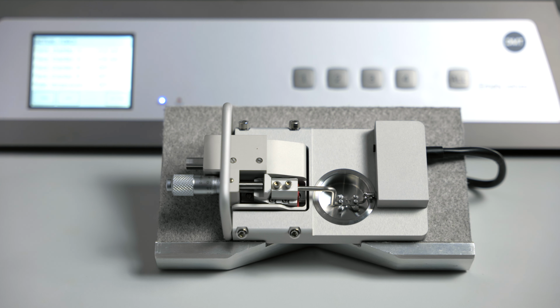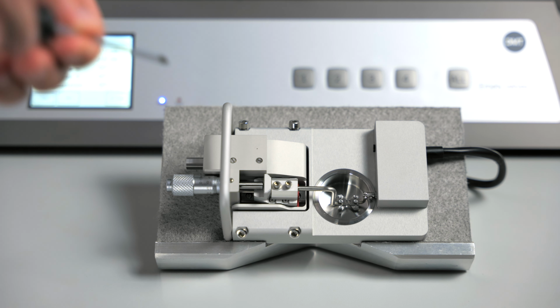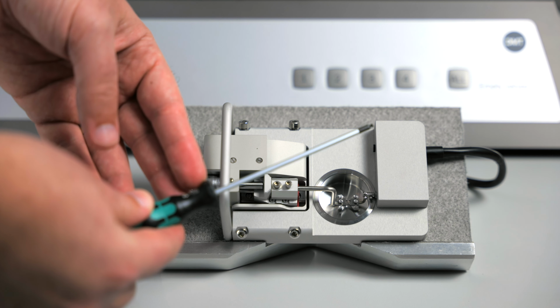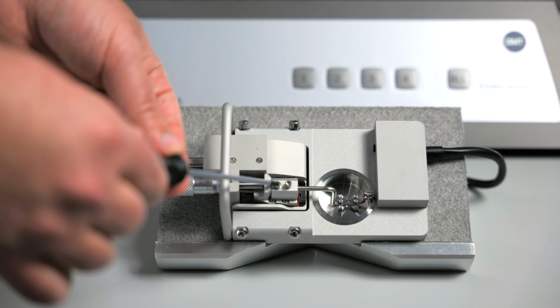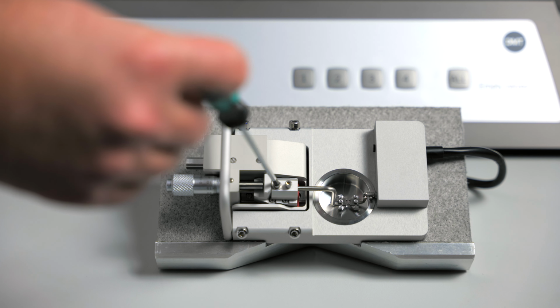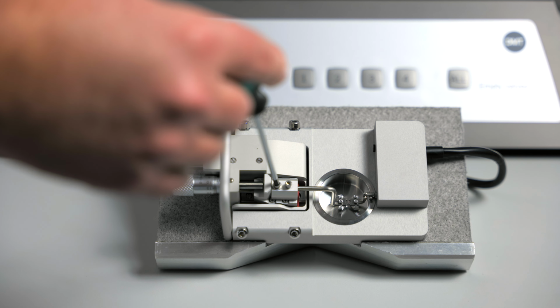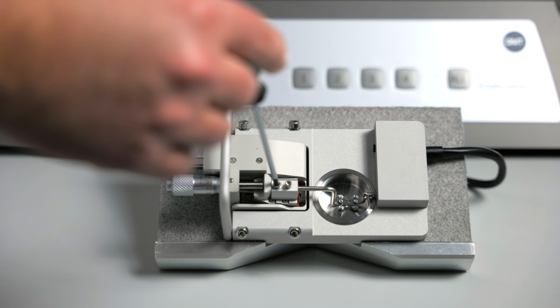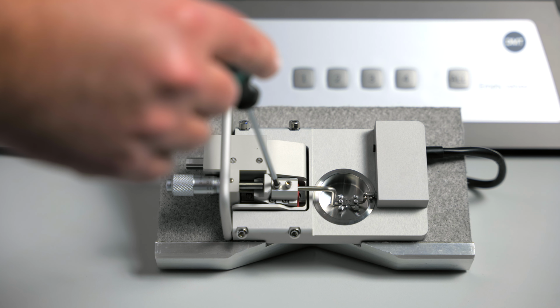There are two types of adjustments. There is coarse and fine alignment. In order to adjust the coarse alignment, you will use your ball end screwdriver and you will loosen the back screw, not the screw used before. This will allow you to drastically move the positioner side mount in many directions. You will use this to get as close as possible to the transducer side.